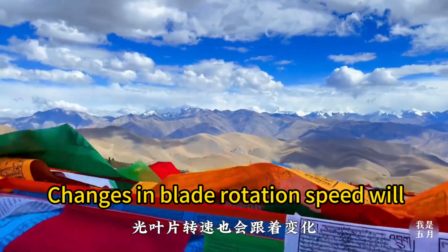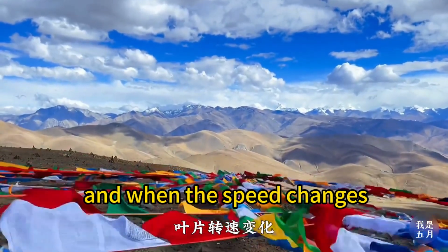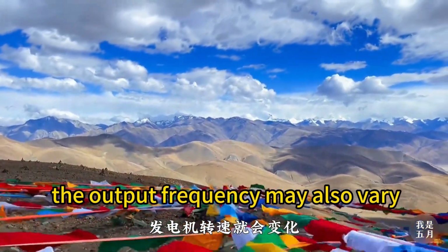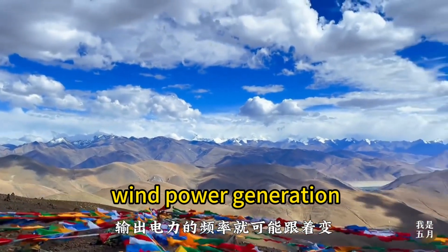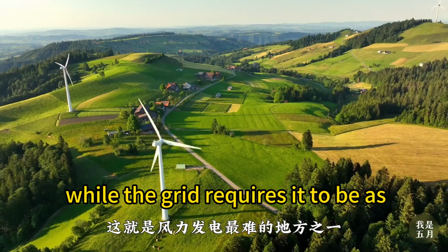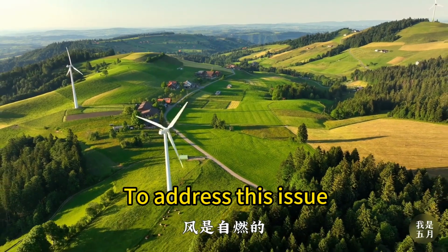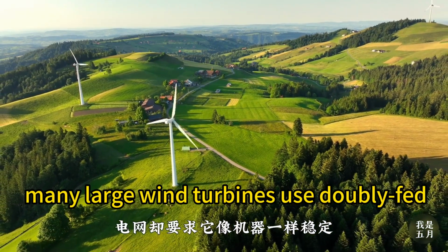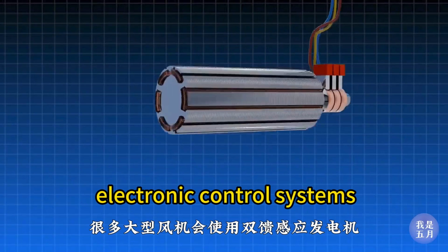Changes in blade rotation speed will lead to changes in generator speed, and when the speed changes, the output frequency may also vary. This is one of the trickiest aspects of wind power generation. Wind is natural, while the grid requires it to be as stable as a machine. To address this issue, many large wind turbines use doubly fed induction generators and power electronic control systems.